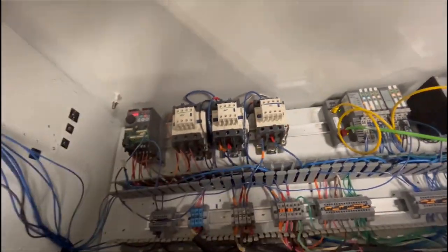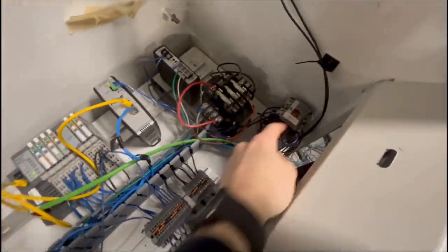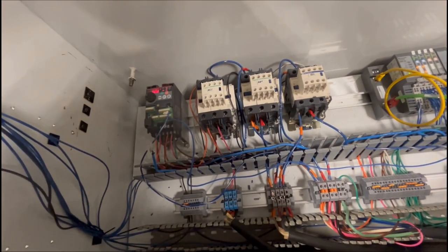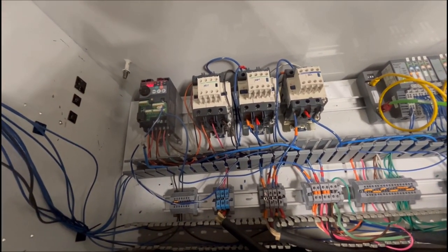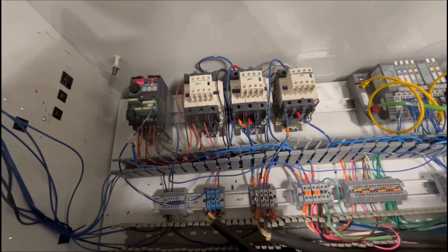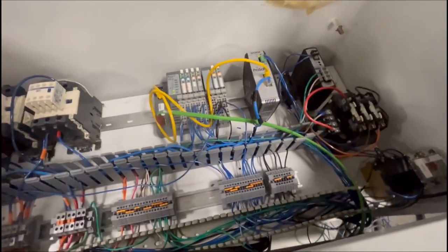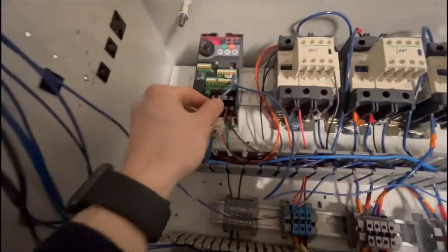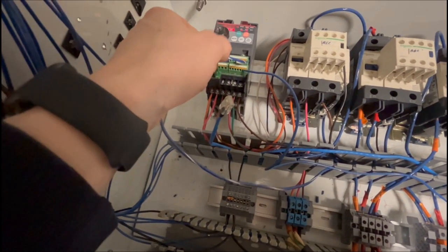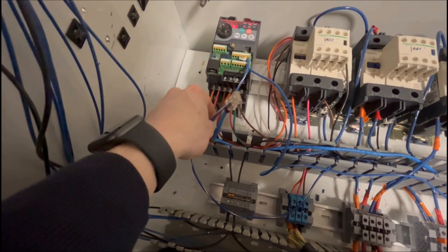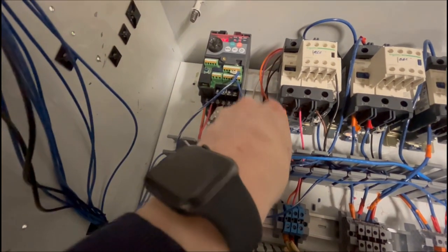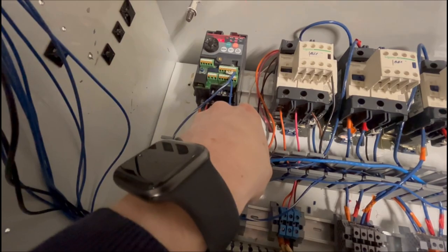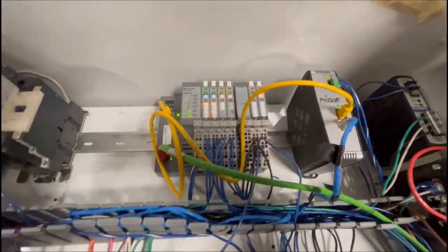contactors. So when I hit my reset button here, we can see this relay actuates, and so does this blower starter, and that's all run off 120 volts. So then we have our frequency drive. This is just powered with 208, 3-phase, and then this is what starts the frequency drive forward, and that's just powered with this relay output card. And then we have it just running back to 24 volt common.